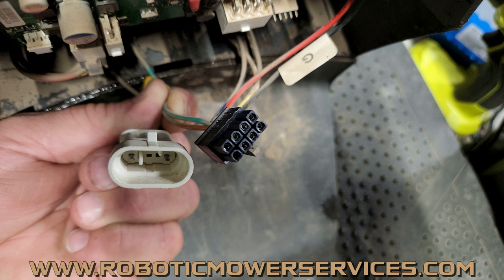So you're testing that entire works right there, from the end where the transformer plugs in all the way to your circuit board. If you don't have high resistance in your positive or negative wires there, then you know that your low voltage cable is good and your charging station harness is good. If you do see a bit of resistance in either the positive or negative side when checking that entire loop...